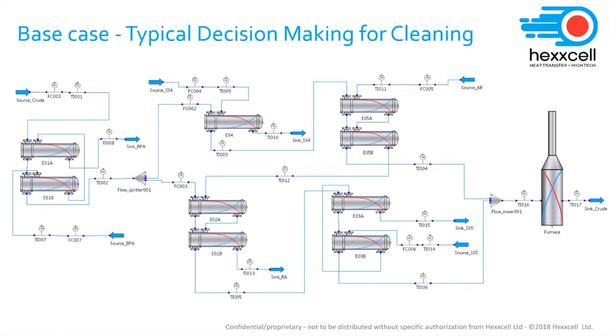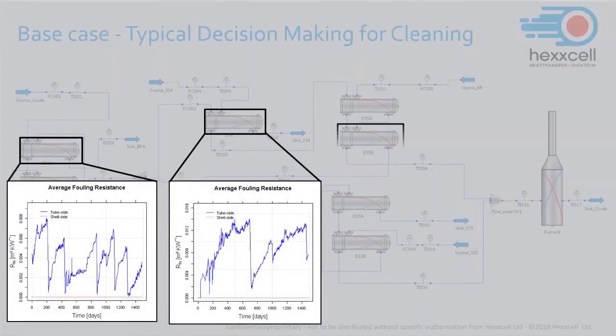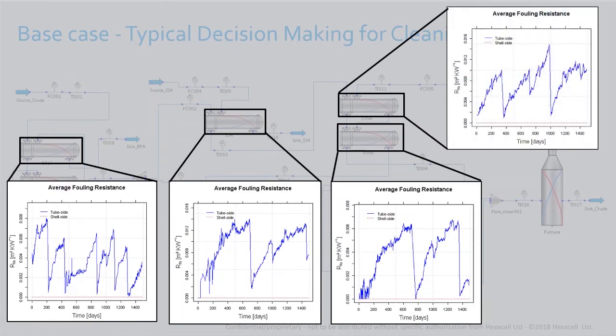So looking at the base case and the 5 heat exchangers in the network considered for the case study, this is how decisions on which heat exchangers to clean and when to clean were made by the refinery. Essentially, they were monitoring the heat exchangers one by one using the fouling resistance, and when certain levels of fouling were reached, they decided to open up and clean that specific heat exchanger that was reaching that specific value of the fouling resistance. Not only is this method based on the fouling resistance, which is subject to the limitations that we have seen before, but these decisions are essentially based on experience. Although they still provide significant benefits, as we will see now, they are not optimal.